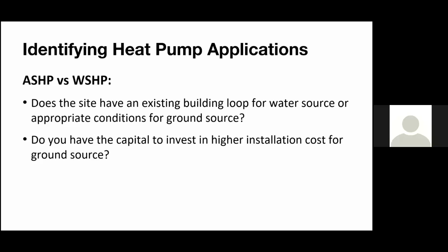Now talking about capital cost differences. When it comes to trying to go all electric, which is what this slide refers to, one of the first things to look at is, is there any existing infrastructure if it's a retrofit building? Is there an existing water source heat pump loop where the pipes can be reused and then possibly converted to geothermal? In those cases, it makes a lot of sense to look at water source and ground source heat pumps, with some of that infrastructure cost right there to be reused.